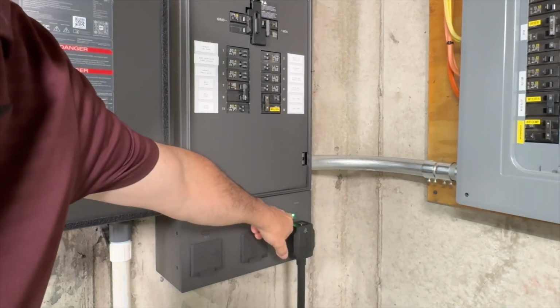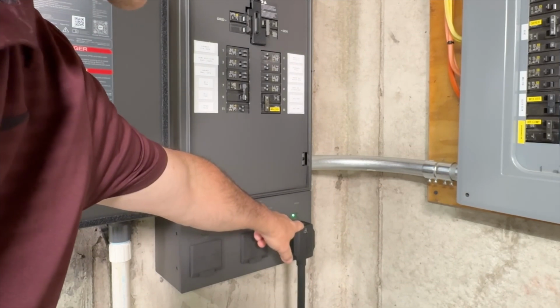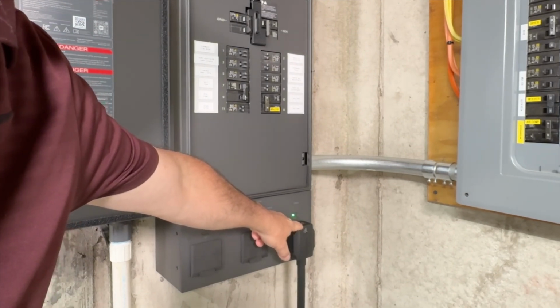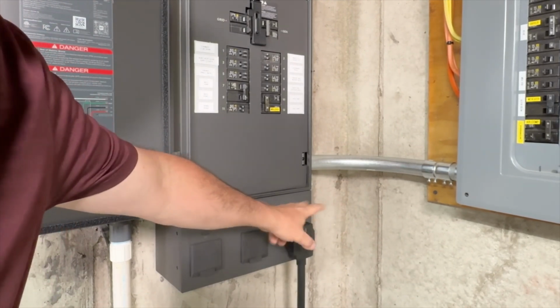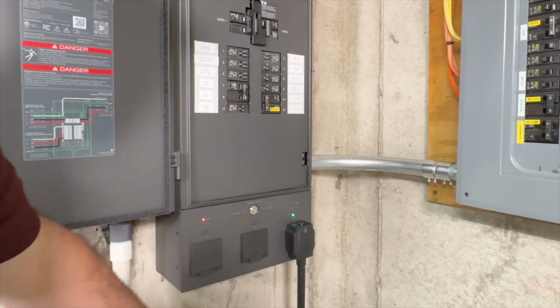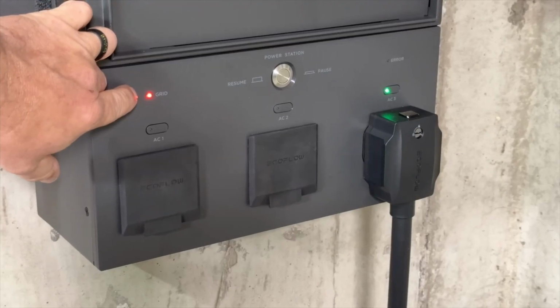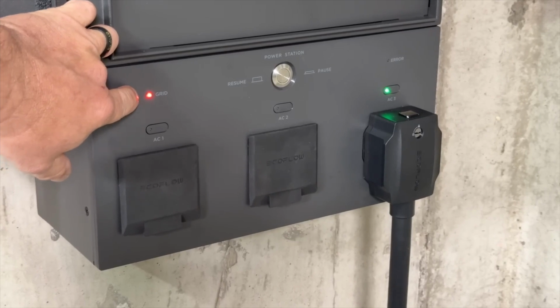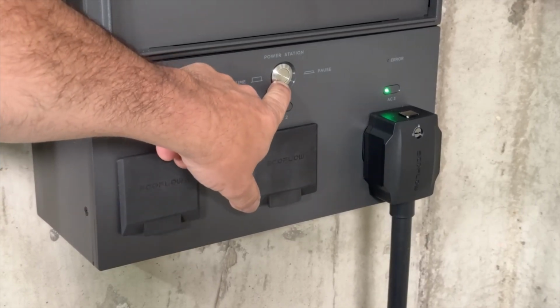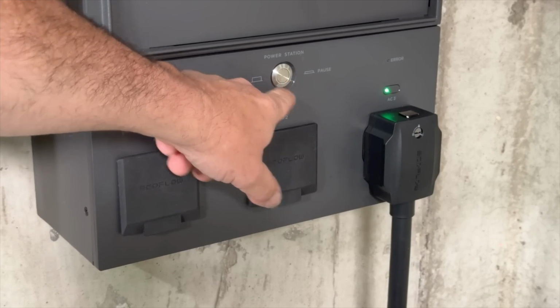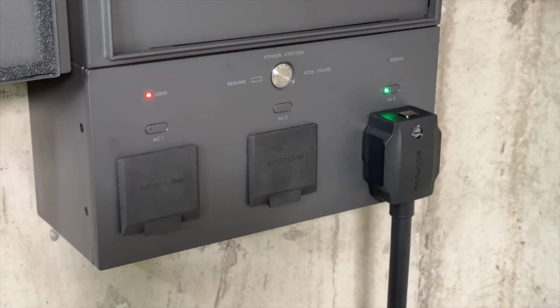Down here we have a green light, which is a diagnostic light — it'll blink red, blink green, or stay solid, and there's a set of codes that go along with that. Over here we have the grid light, which is red, telling you the grid is dead. And there's an emergency power station switch here, which if you hit it, disconnects everything from the transfer switch and kills everything.